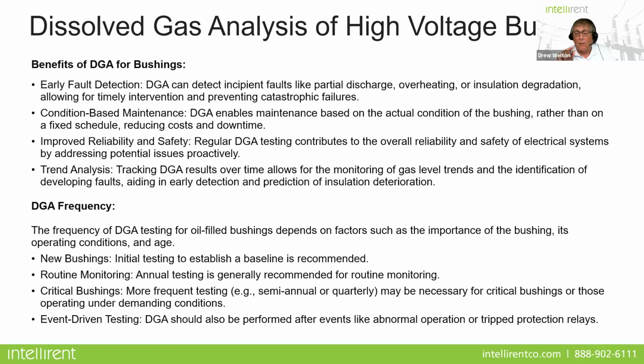If you have critical assets, GSUs, or depending on the conditions, if you're in a high caustic environment, or if weather-related incidents are common, then you may want to increase that frequency of testing. Event-driven testing is also important.